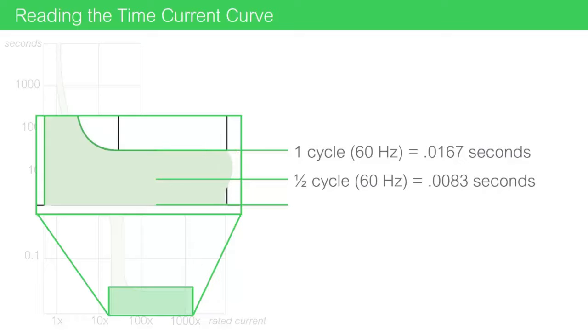Now, why do some time-current curves show a line at one cycle and at a half cycle? Circuit breakers that share a frame and the same amperage rating can have differing short circuit protection levels. This will be discussed more in the later course, Selecting Circuit Breakers. But for now, we wanted to point out that some circuit breakers may share the same time-current curve, with notes on it to point out differing trip values.